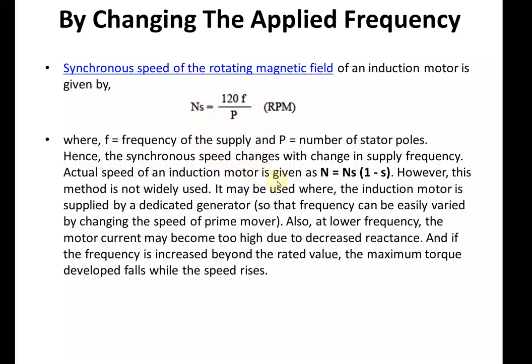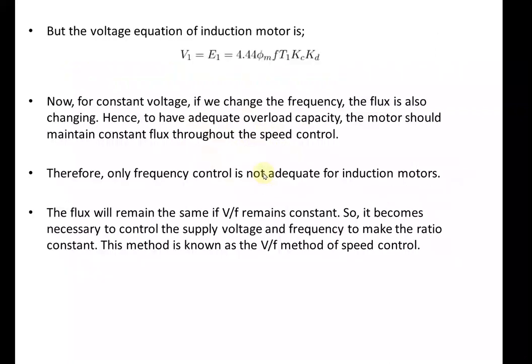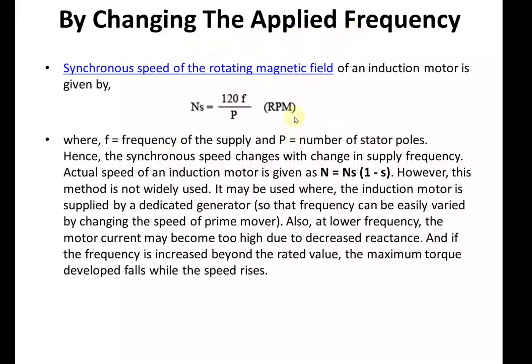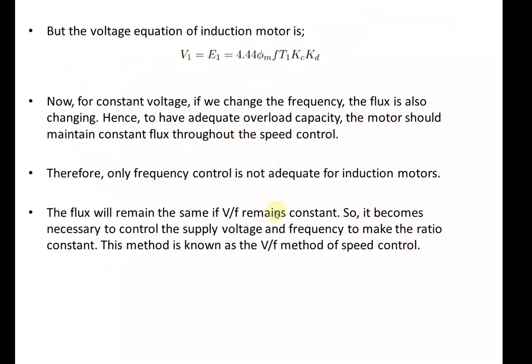This frequency-only method is also disadvantageous and not very popular. So there is a new combinational technique: we have to combine both techniques — change the applied voltage with respect to the supply frequency. This method is called the V/f method. We know that the voltage equation of the induction motor is: V = 4.44 × f × Φm × T1 × Kc × Kd, where Kc and Kd are coefficients.